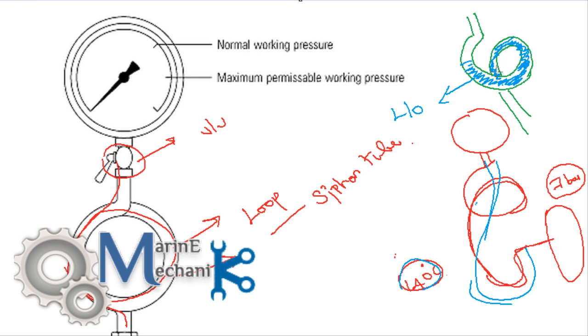Now for a boiler we always have some water filled up in this loop as shown in this picture. So as the steam comes through this passage from the boiler, it heats up the water or in turn the steam gets condensed. The superheated or dry saturated steam does not get in touch with the bourdon gauge of the pressure gauge directly. The contact is through the water so the bourdon gauge is saved from getting damaged. That's the purpose of this siphon tube.